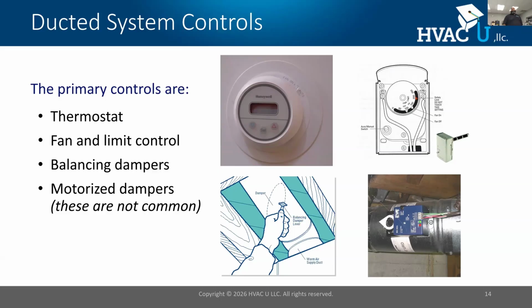The second control, which maybe is not understood by many auditors, is that the furnace has some type of limit control. On older equipment, it was a fan limit. Now it is the limit. What does the limit do? We'll talk about that. What about balancing dampers? They're really important to have, and oftentimes we don't see them. And in some cases, we've solved comfort problems by modifying the duct with motorized dampers.